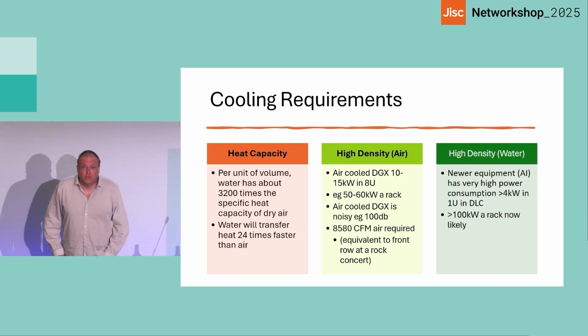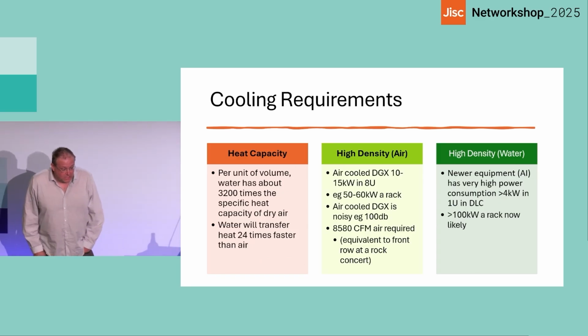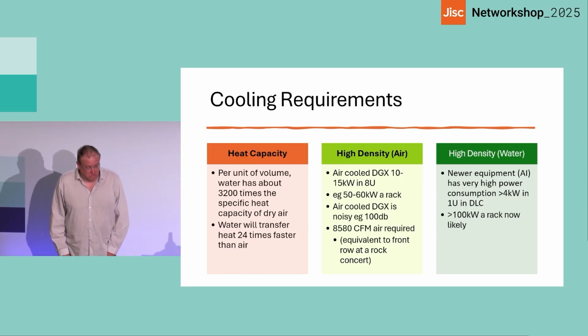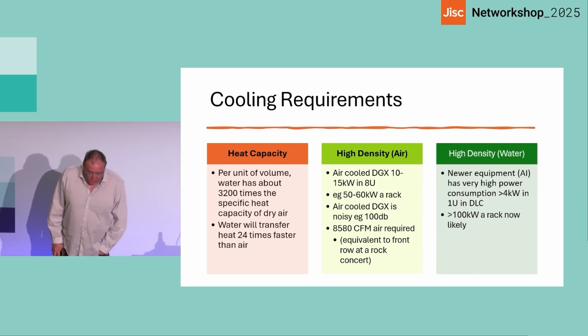And as you can see up the top, there's high density air systems, one of those DGX units, one of the latest ones, one of those NVIDIA Hopper ones, is 15 kilowatts in 8U. It's a lot of heat, and you're going to get 60 kilowatts a rack. That's about the limit of those air cooling units, and they're going to sound like a jet turbine. You don't want to be near them.